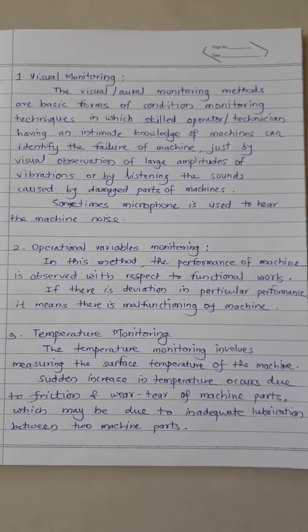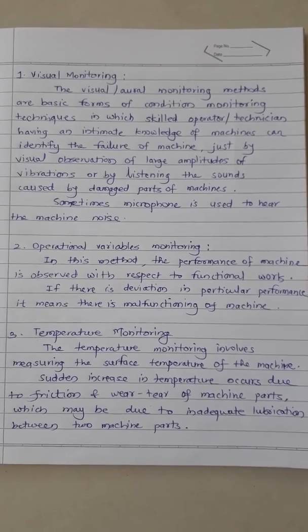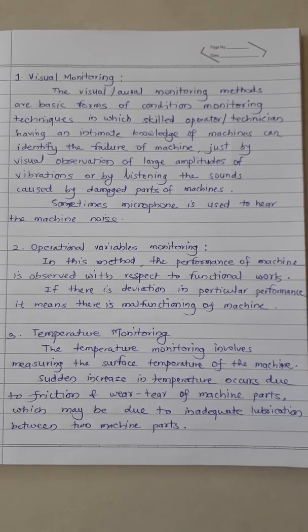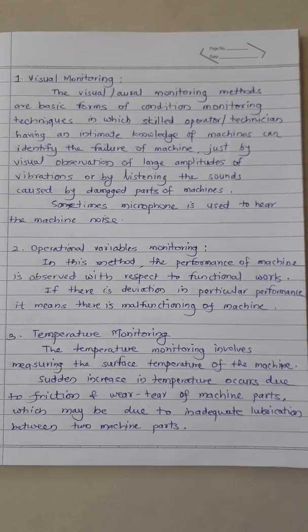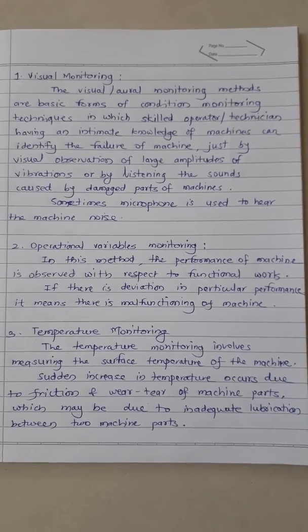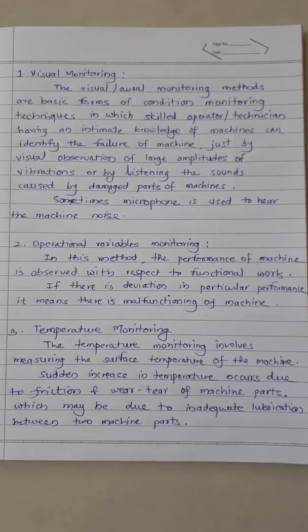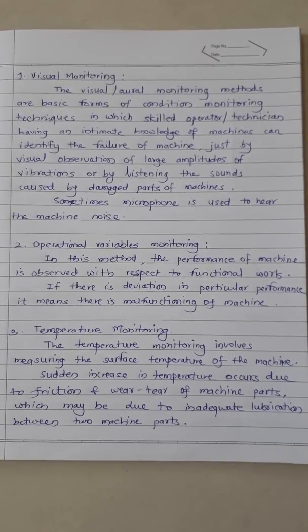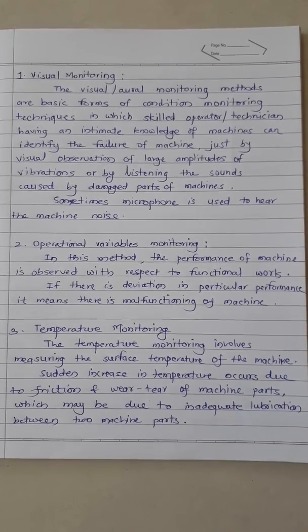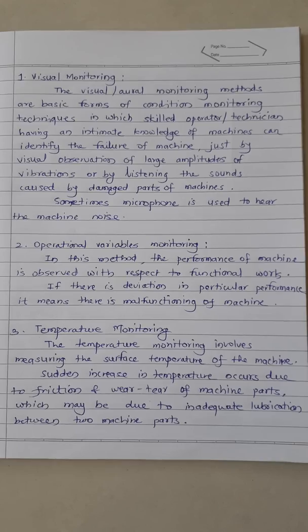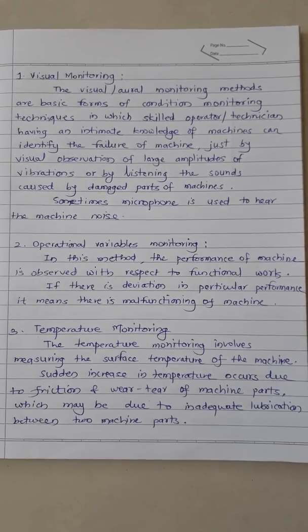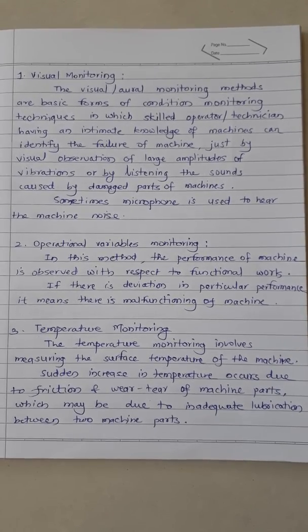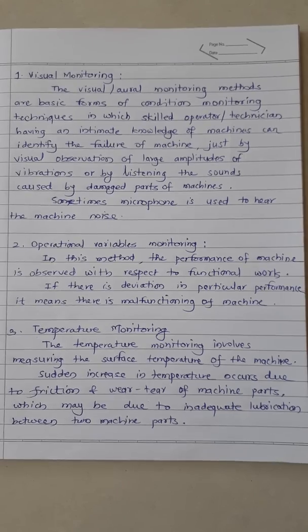Temperature monitoring involves measuring the surface temperature of the machine. A sudden increase in temperature occurs due to friction and wear and tear of machine parts, which may be due to inadequate lubrication between two mating parts. If at a particular temperature the machine is working, and temperature suddenly increases, it indicates friction or wear and tear in parts, possibly due to inadequate lubrication. Through temperature monitoring, we can understand the condition of the machine.